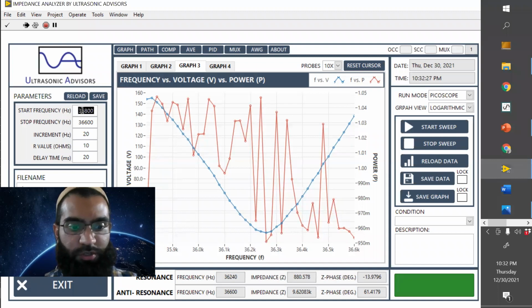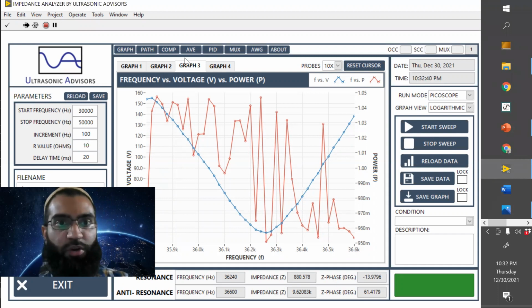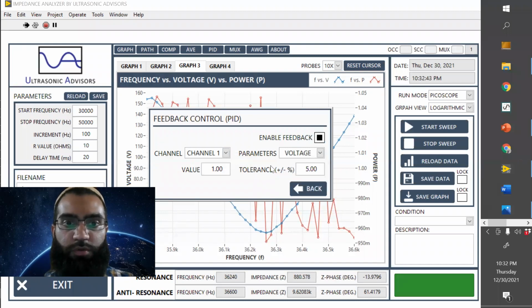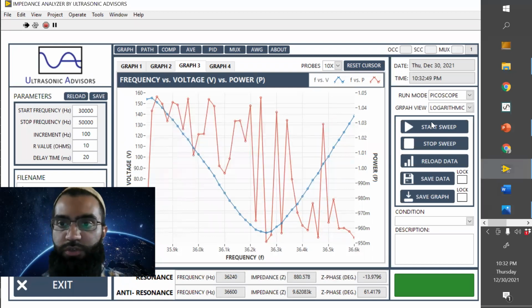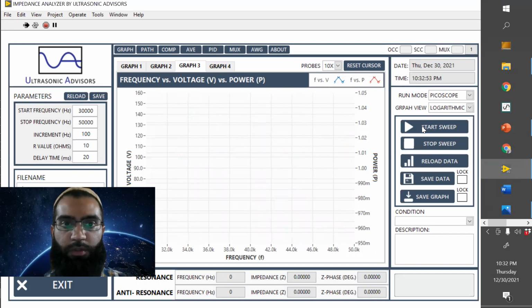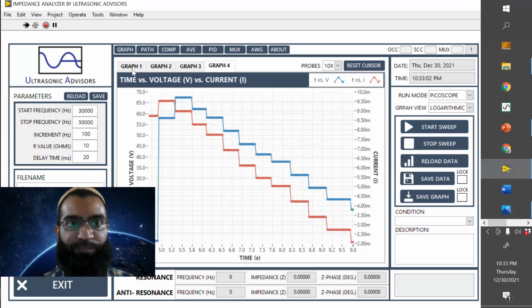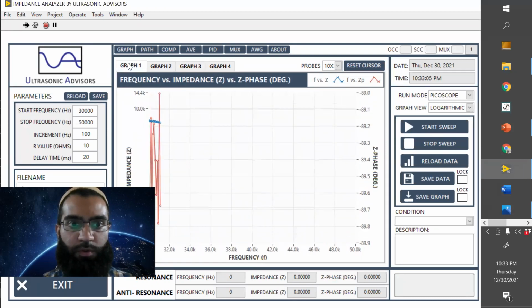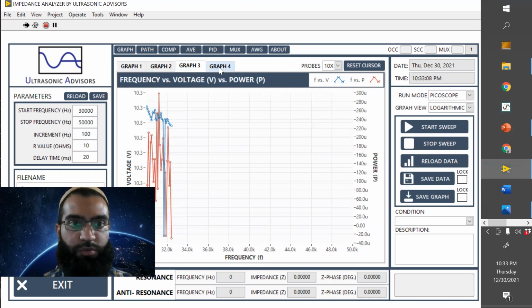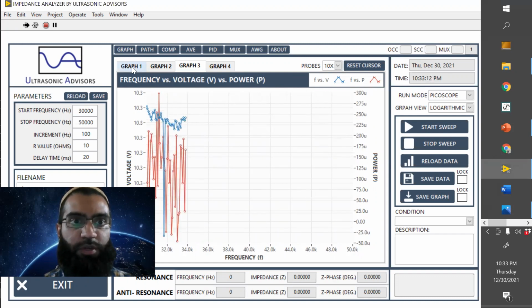The way I would redo a characterization is just do like a 30,000 hertz to a 50, with increments of 100. And this is a similar process that you might do for investigating your transducer in whatever system you're using. I would do voltage, and for this type of device, I would just go 10 volts, which shouldn't be too much. So let me just run that sweep. All right.